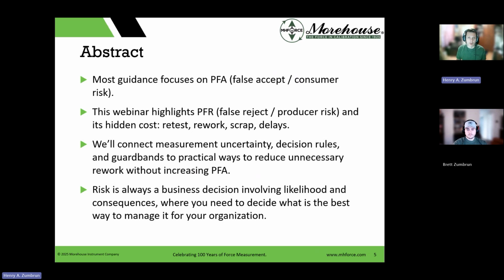That's usually the large uncertainty guard bands that, and this is my biased opinion, may be too aggressive. And then your PFR, guess what? You put an aggressive guard band on something, and now you're going to reject more items that are actually good, say they're bad, and adjust them. So this webinar is going to highlight the false reject, producer risk, hidden cost, and rework. We'll connect measurement uncertainty, decision rules, and guard bands.